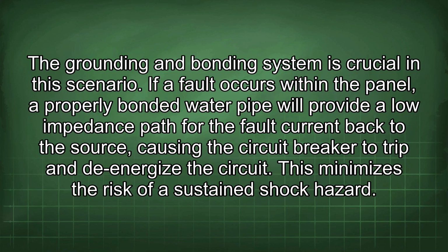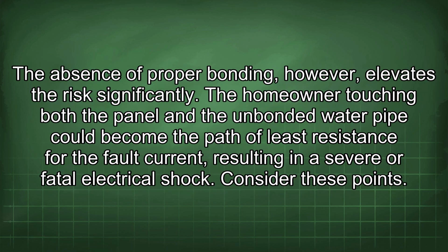The grounding and bonding system is crucial in this scenario. If a fault occurs within the panel, a properly bonded water pipe will provide a low impedance path for the fault current back to the source, causing the circuit breaker to trip and de-energize the circuit. This minimizes the risk of a sustained shock hazard. The absence of proper bonding, however, elevates the risk significantly. The homeowner touching both the panel and the unbonded water pipe could become the path of least resistance for the fault current, resulting in a severe or fatal electrical shock.